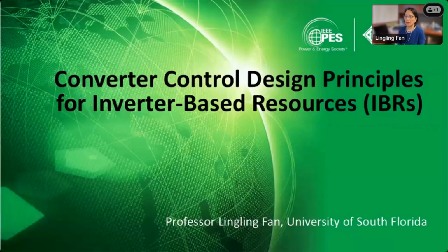They don't call it GFL, GFM. They don't want to differentiate just by how you do synchronization. They don't care about internal stuff. They just care about whether you can provide grid functions as we designate. The grid function you designate is basically, can you provide frequency support? Can you provide voltage support? If you can, you just call it an advanced grid support inverter, something like this. So the short answer is yes, you can do that, because you can just change the power reference and make it modulated by FP droop instead of the other one, the PF. That's it.